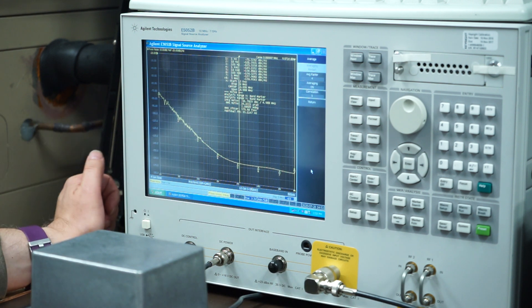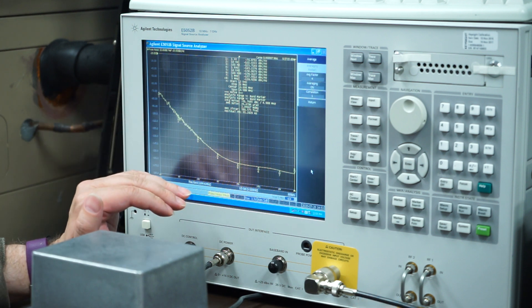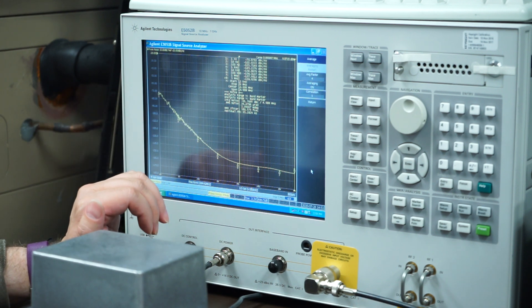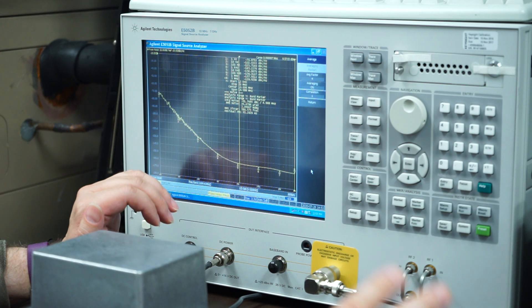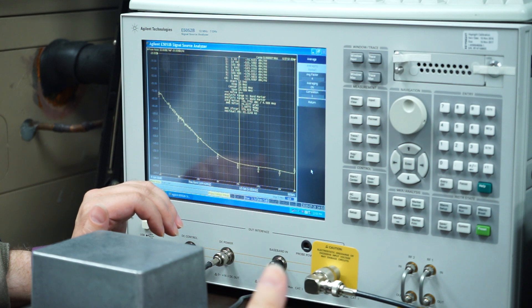One of the other issues in the industry is not only having the instrument, but knowing how to use it. In this case, we're getting the anticipated curve. It's a fundamental crystal. We shouldn't see a bunch of other spurs in it. If we did, we'd have to determine whether they're part of our device or part of our test and measurement setup.